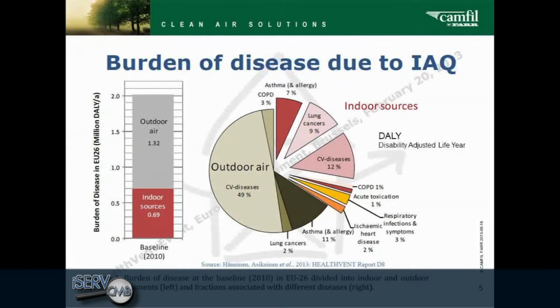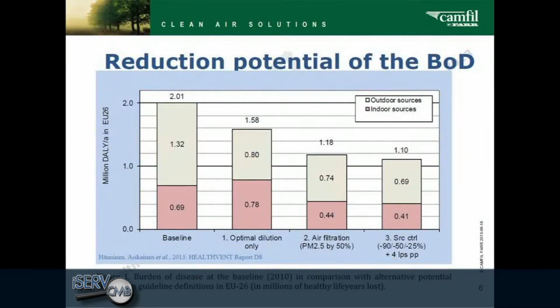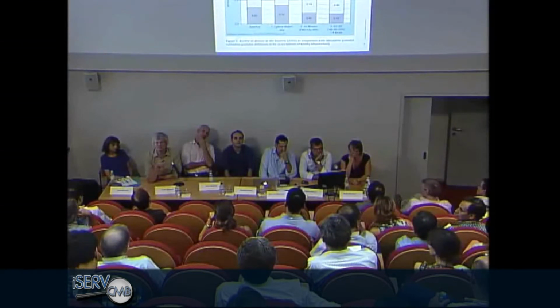Just to draw quick attention to the solutions that have been offered, you can hopefully see those 4 bars there. The first bar gives you the ambient background pollution. The second bar gives you the reduction based on optimum dilution or ventilation of the air. The third bar there gives you the effect of having a reasonably efficient filter system. It says there PM2.5 reduction by 50%, which would require a good F7 class filter as a minimum. And when I say good F7, I mean one with the correct media, microfiber glass. And that will give you your 50% reduction, and that again will ensure that there has been a good reduction in the health damaging particulate.